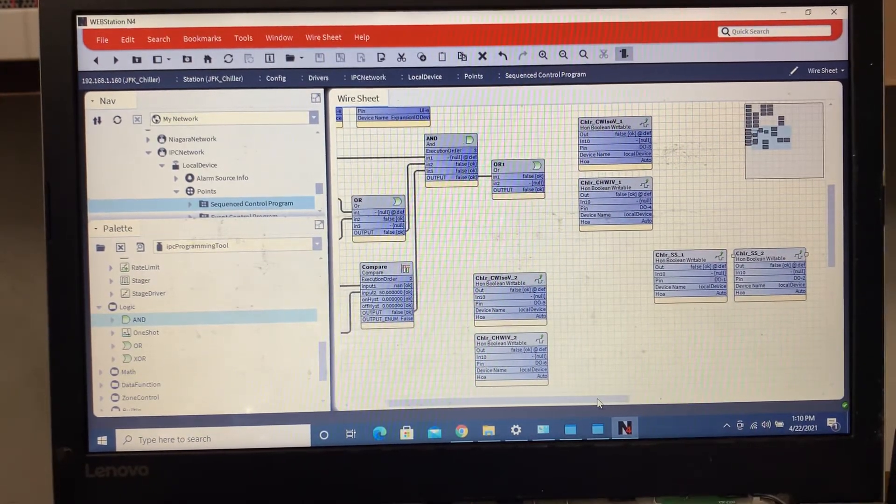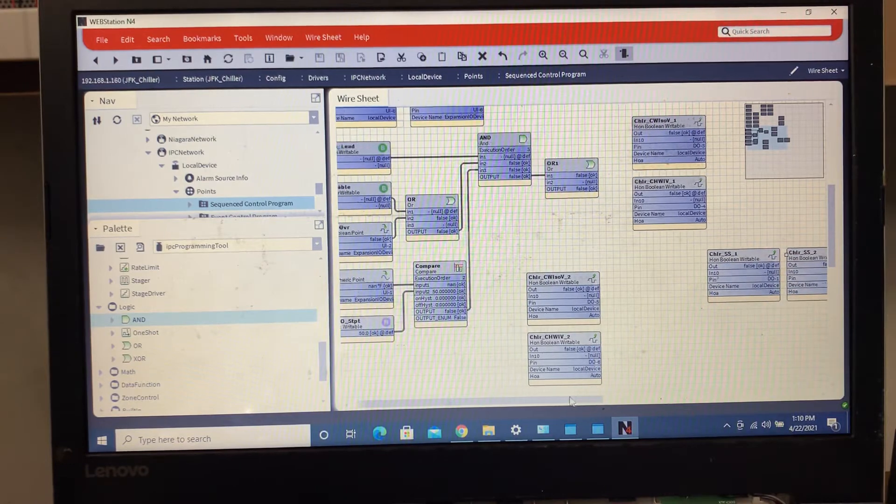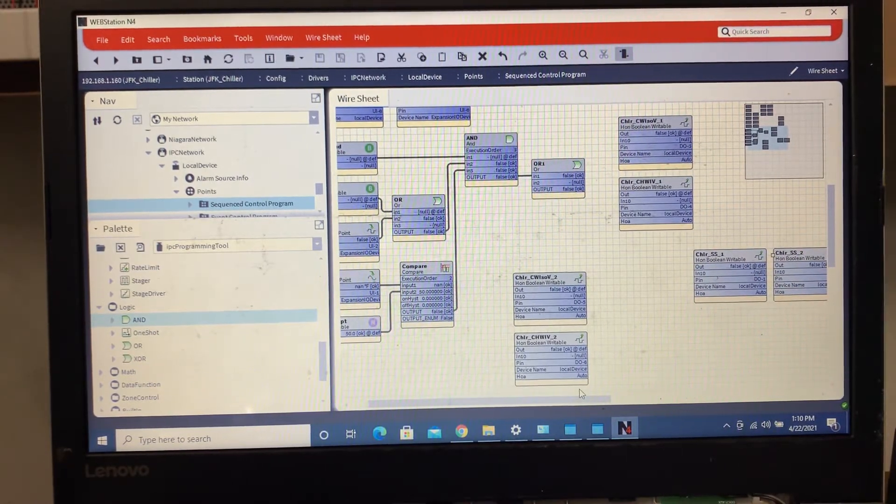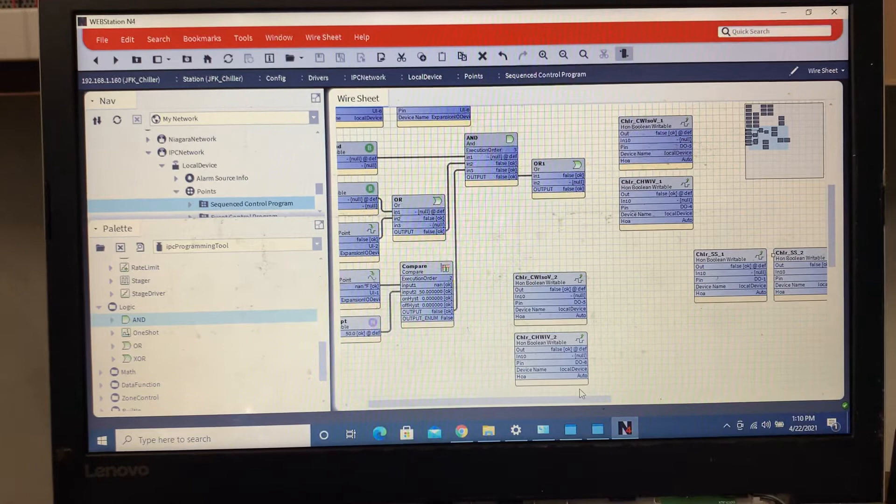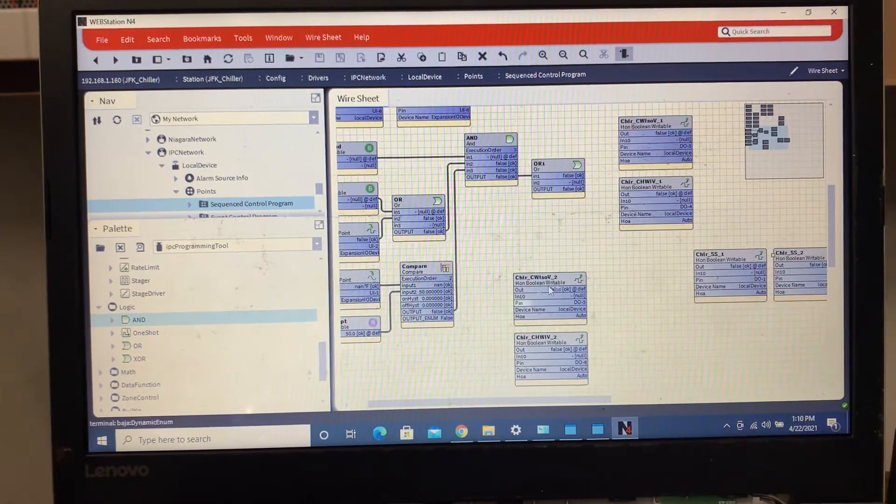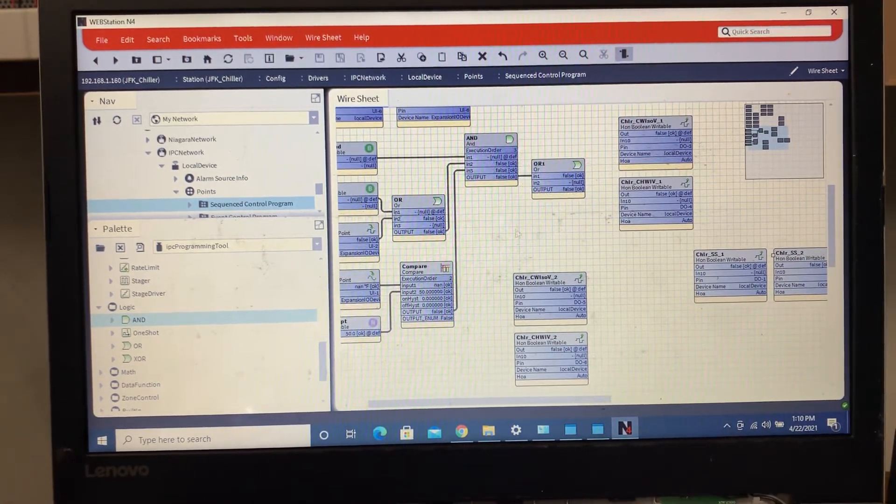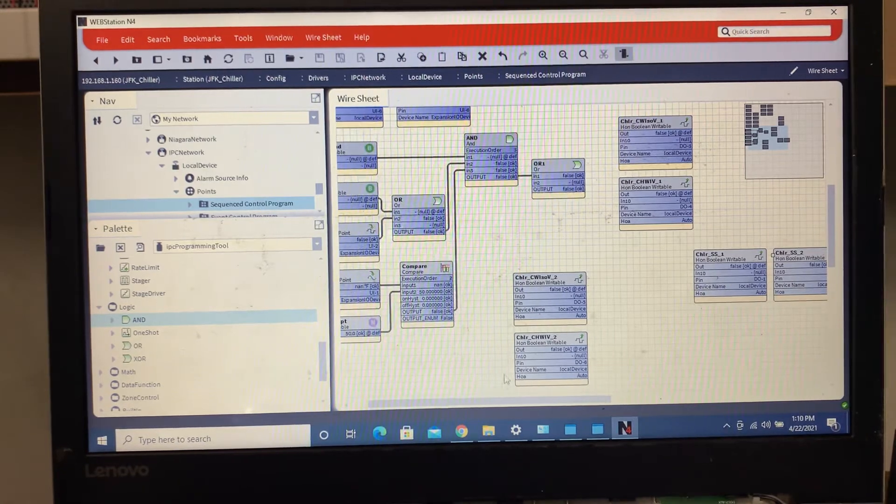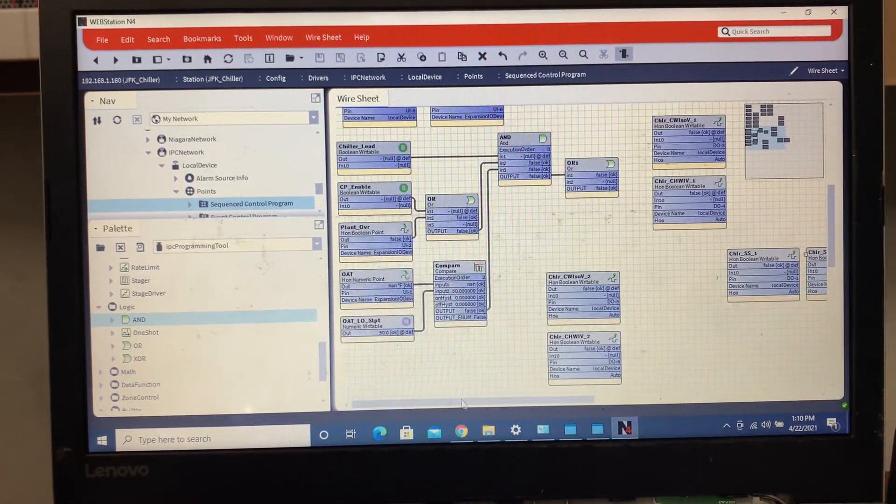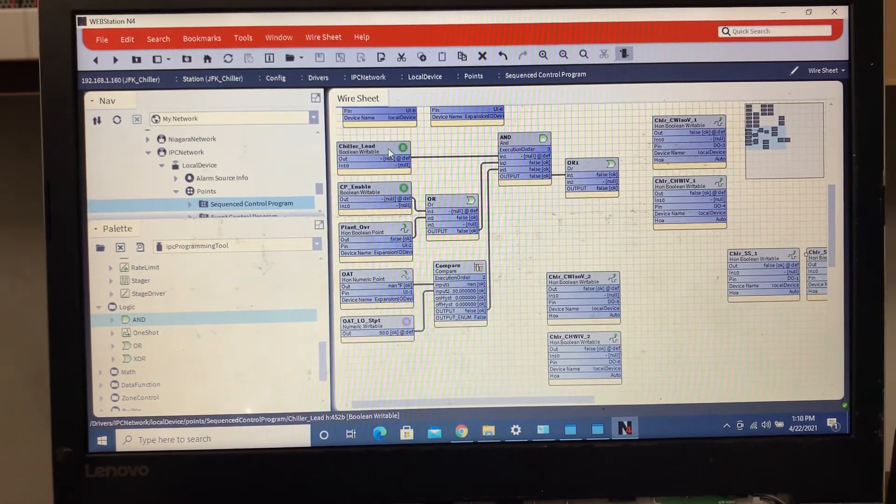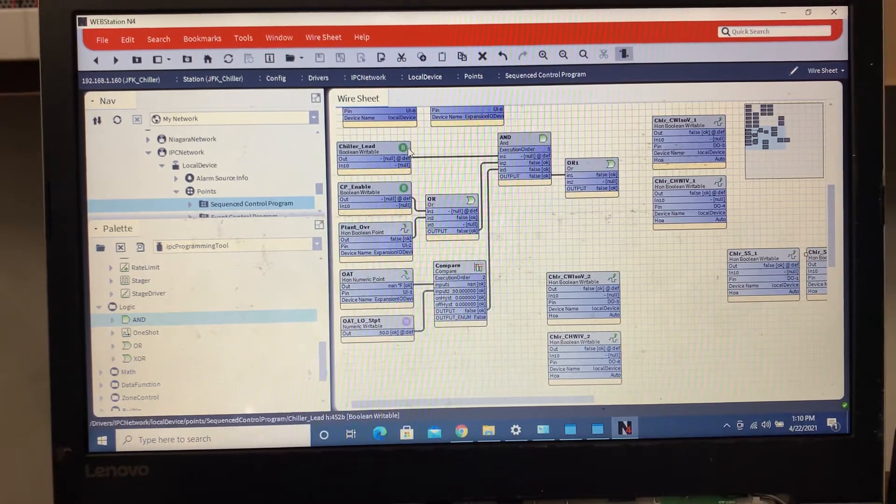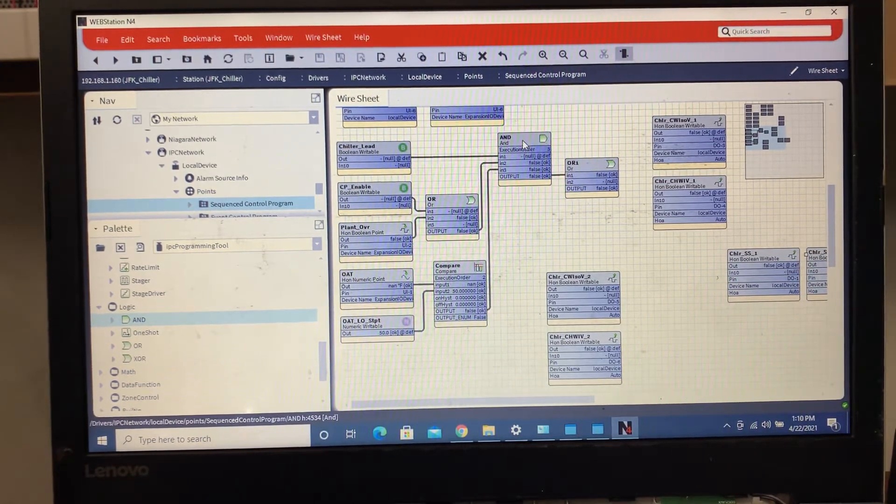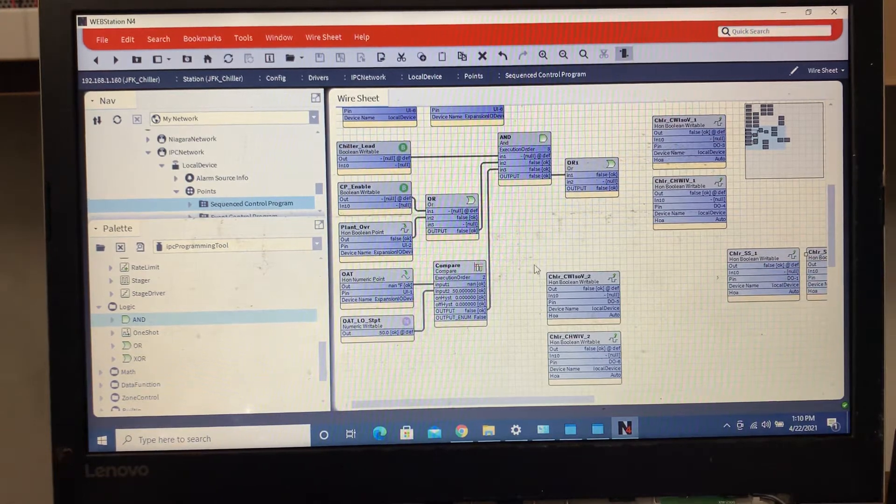With this one it's going to be based on maintaining a supply water temperature, so we'll create a whole other setpoint later on for that. But I just wanted to show some of the basic programming that we're going to do with this. So we got our chiller lead, so chiller one will be the lead which will be true. What we'll do is we'll make this AND block again and we'll make it a NOT as input one, so that way whenever the chiller lead is false it'll be true in the AND block.